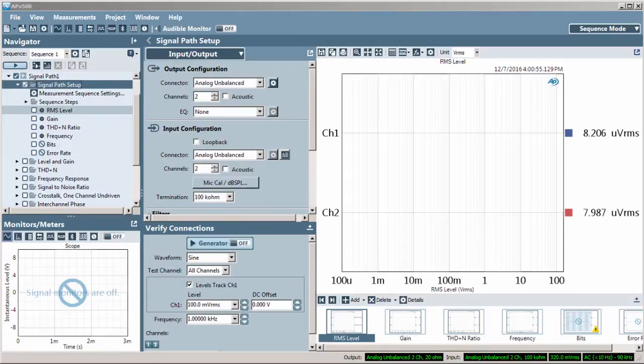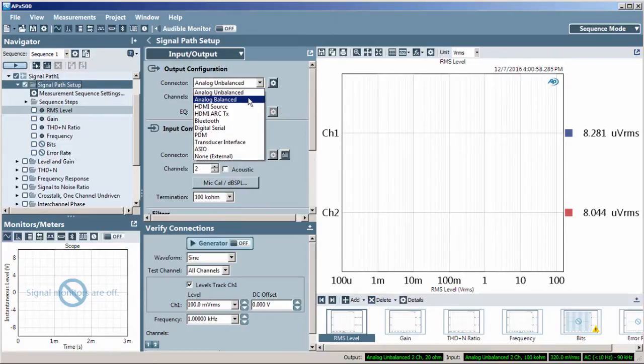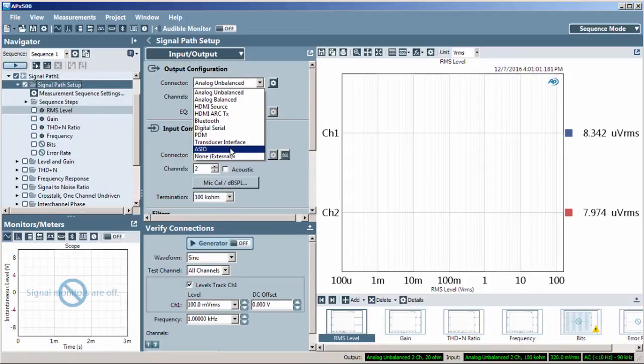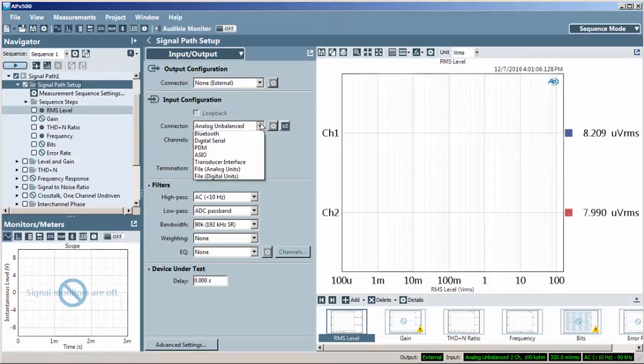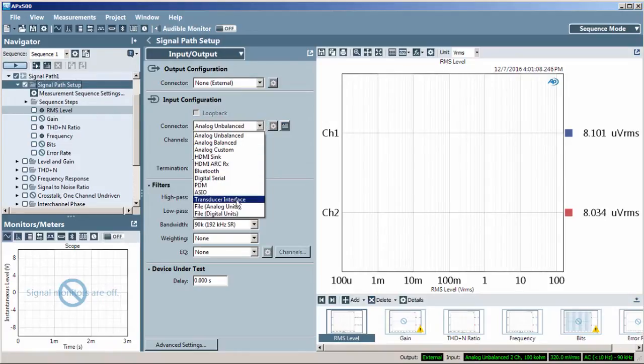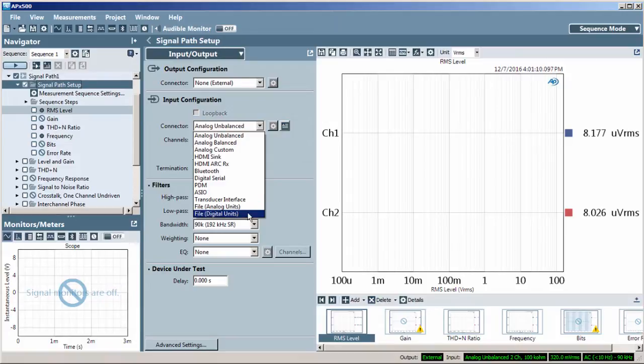While APX analyzers have many physical input and output options, you can also input WAV files for analysis. The use case could be a device under test which records audio data to a file, or analysis of signals acquired off-site or offline from the APX analyzer.